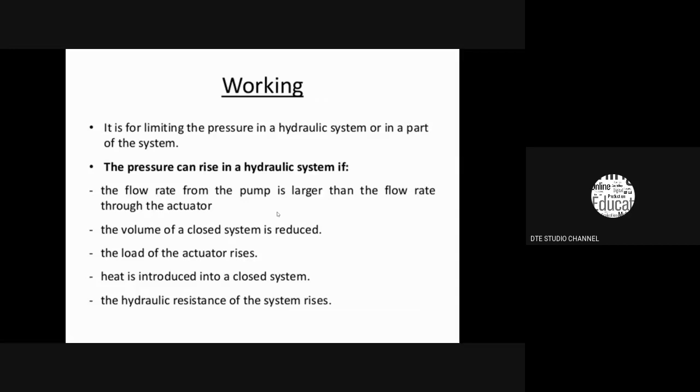Pressure relief valve is for limiting the pressure in a hydraulic system or in a part of the system. The pressure can rise in a hydraulic system if the flow rate from the pump is larger than the flow rate through the actuator. There must be a synchronization. The flow rate through the pump and the flow rate through the actuator must be equal. Otherwise, the pressure may vary.